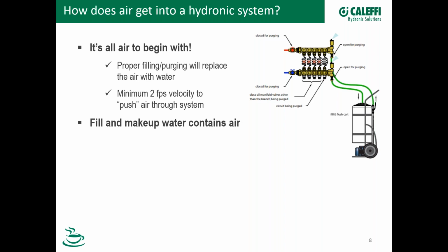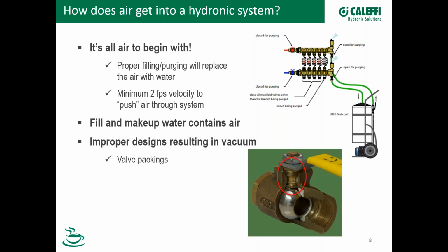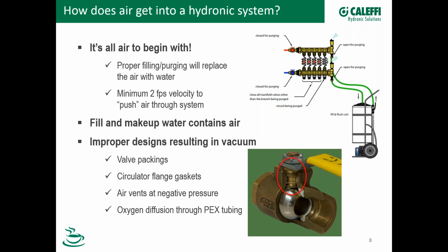And remember too that all the fill water and the makeup water will contain air. That's just a fact. It's part of the game. And another way that air can get into the systems after we've filled and we're running is in vacuum areas. So for example, a valve packing, if we draw a vacuum where we have a ball valve located like this picture here, if the packing is a little bit worn, you can pull air into the system through that. The same thing for circulator flanges, for example, if they're not quite sealed properly. And if you draw a negative pressure at an air vent and you don't have an anti-suction cap, we'll cover those in a few slides too, you can pull air in the system as well. And don't forget too that PEX tubing, if you don't have the type of tubing that has the barrier for oxygen, you can actually get oxygen in through the system, through the tubing.